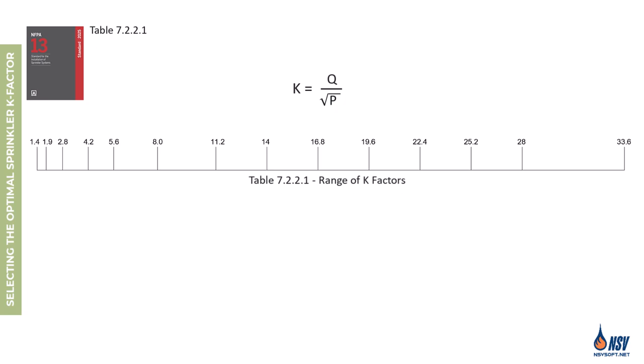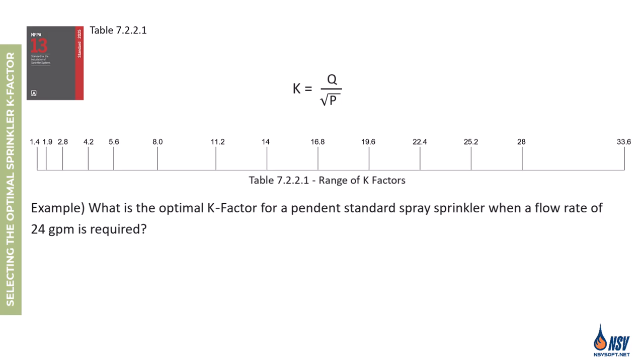To determine the optimal K factor, it can be calculated based on the required flow rate and the minimum acceptable pressure. The next step is to select the nearest smaller standard K factor value according to Table 7.2.2.1. For example, if a standard spray sprinkler requires a discharge of 24 gpm, the calculated K factor would be 9.1. Within the acceptable K factor range, this value falls between K = 8.0 and K = 11.2; therefore K = 8.0 should be selected as the optimal K factor. As reviewed in this video, selecting the right K factor is crucial — sometimes increasing it helps, other times decreasing is better. Designers must evaluate system parameters to reduce hydraulic demand and ultimately lower the system's overall cost.